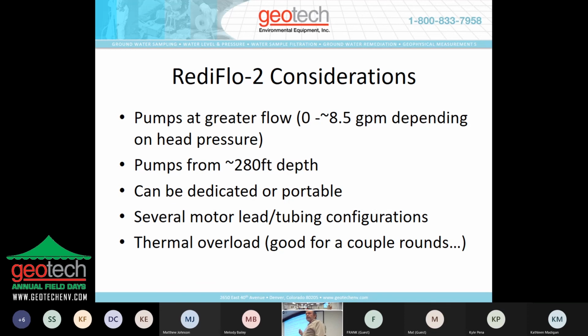Things to consider about the RediFlo-2. It pumps at a greater flow, 0 to almost 8.5 GPM. And it's going to depend on head pressure as to what kind of flow rate you get. And that's true of any pump, not just this particular pump. It can pump from 280 feet, which is a pretty good depth considering it'll fit in a 2-inch well. 2-inch wells offer a lot of limitations to a lot of applications, which we'll cover a little bit further in.